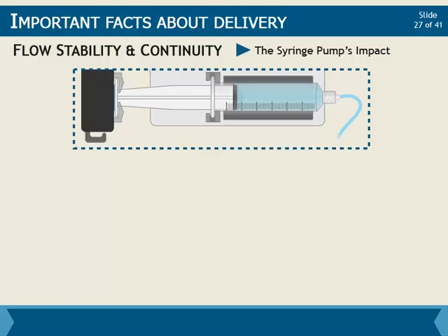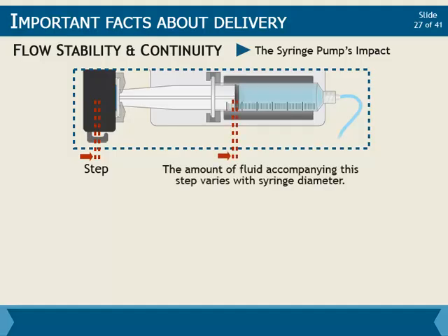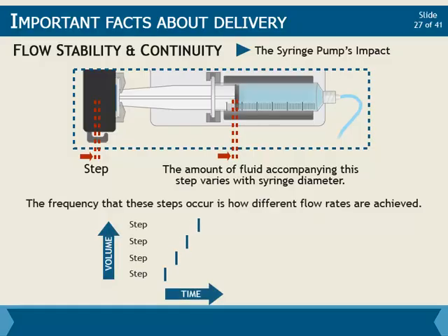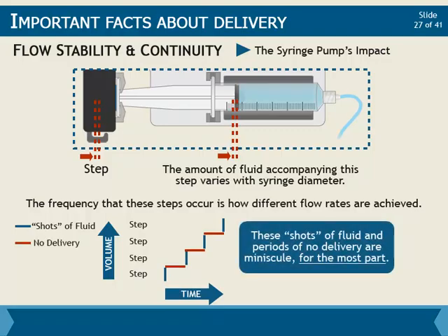Each time the motor moves in a syringe pump, it serves to push the syringe plunger a tiny bit. We will call this movement a step. The size of this step is less than a micrometer, and it is the smallest movement achievable by the pump. The amount of fluid accompanying this step varies with syringe diameter. The frequency that these steps occur is how different flow rates are achieved. Conceptually, we can think of medication being delivered in a series of tiny shots of fluid and short periods of no delivery. However, these shots of fluid and periods of no delivery are minuscule for the most part.